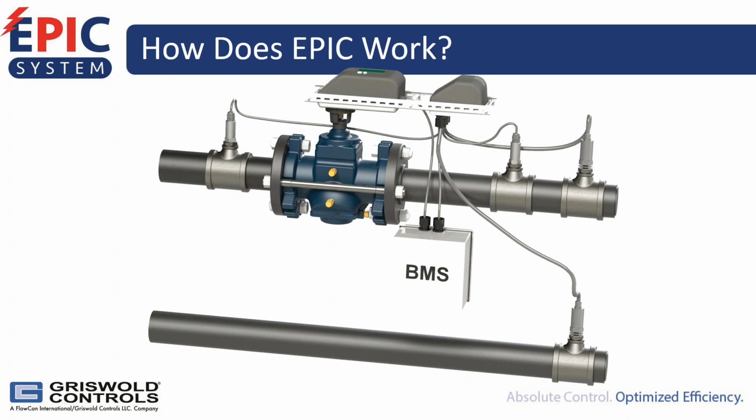Well, when the load changes, a thermostat on the wall senses the load change whenever there's a temperature change or when the thermostat is adjusted. And this changes the coil's airflow. And as the coil CFM changes, the delta T of the water changes. And so the temperature sensors read that change, and the EPIC controller adjusts the valve to bring the delta T back to the design specification.